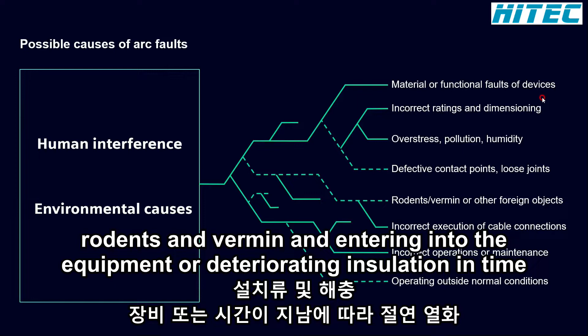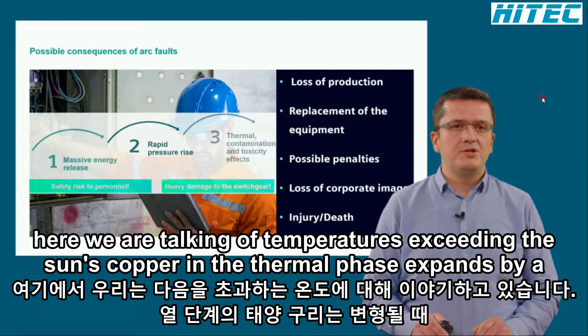Many of you should have seen disaster videos showing arcing faults and their consequences on human beings or on the equipment and its environment. What you have seen there is an explosion with a dense light, fire, and smoke. What happens inside the equipment remains behind the scenes, beyond what you have seen. Here we are talking of temperatures exceeding the sun's. Copper in the thermal phase expands by a factor of 60,000 times when it transforms from solid state to plasma formation.